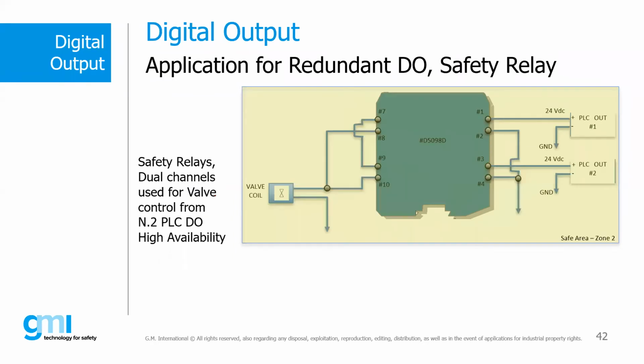In the next slide, we encountered a digital output application where we were asked to be able to control a final element, typically a valve, with two digital output cards. The final element, normally energized, must be de-energized only if both digital outputs give the switch off command. This solution, studied to obtain high availability of the process and to keep the plant always active in order not to have losses in production cost, can be obtained through a double channel safety relay with the output contacts placed in parallel. In fact, this way, the load will be de-energized only if both digital outputs give the shutdown command.